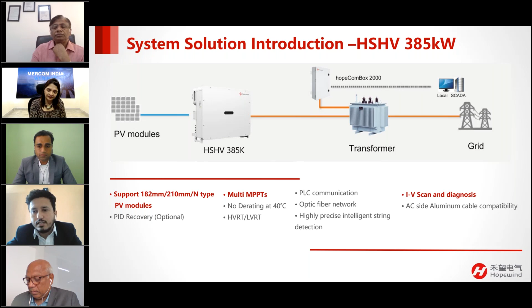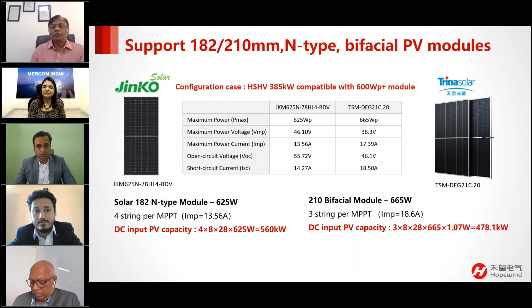For your better understanding, we have taken two types of modules having different wafer sizes and different currents. In the Jinko module, the IMP current is 13.56 ampere, and in the Trina module, it's 18.6 ampere. Our 385 kilowatt model has four DC inputs with 60 ampere current each MPPT. For the first case, we have used all four DC inputs, but for the second case, we have used only three strings per MPPT to increase the DC input current to 20 ampere. So a higher peak module can easily be connected as we decrease the number of strings per MPPT, which increases the current to 20 ampere.